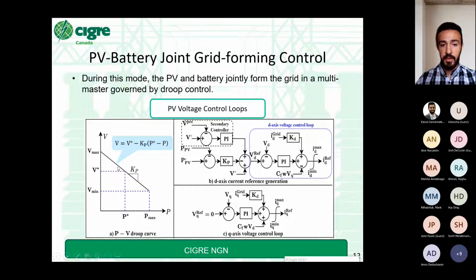Looking at here, this is the PV droop curve. D and Q axis, similar outer voltage control loops, are going to be used in the battery energy storage system, where here the VD reference is going to be derived by the PV droop curve. And on top of that, we can see that there is a secondary controller in order to restore the nominal voltage of the grid.